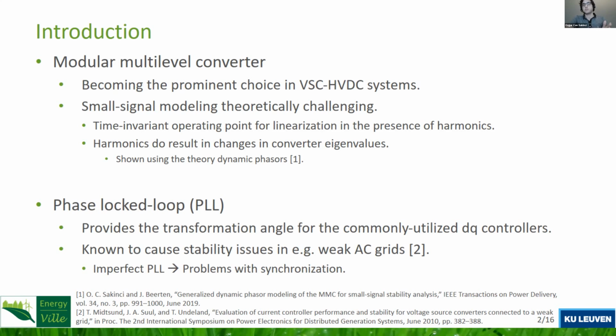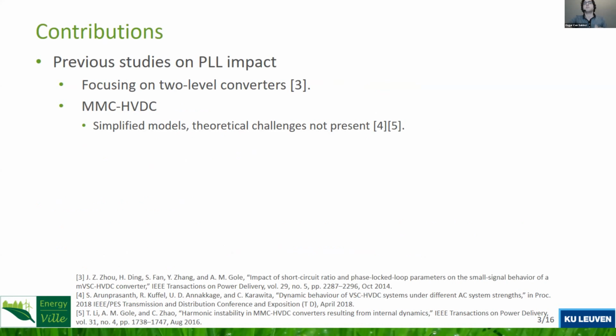When the AC grid is weak, an imperfect PLL would mean the wrong synchronization angle is calculated, potentially causing synchronization problems between the controllers and the system, leading to instabilities. The impact of the PLL on the small signal stability of VSC HVDC systems has been studied previously in the literature, but the main focus was on two-level converters.